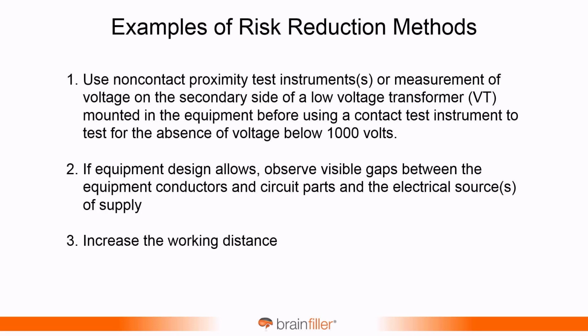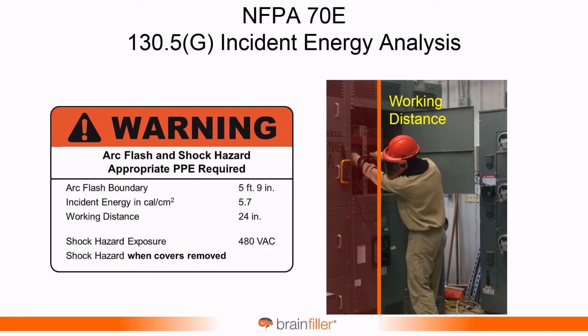Increase the working distance. Now the working distance is really critical for a lot of this, because when someone calculates the incident energy, it's actually based on the distance from the source of the arc flash to the worker's torso and head. And so increasing the working distance, if possible, may go a long way towards helping out.